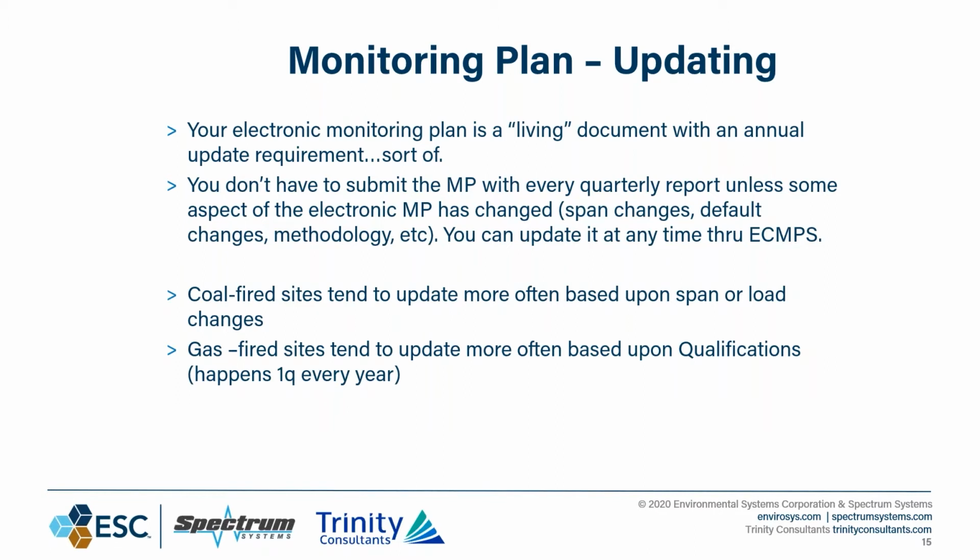Now, again, with talking about updating your monitoring plan, the electronic portion is a dynamic publication with an annual update requirement. You don't have to submit your monitoring plan with every quarterly report like you used to in the flat file days, unless some aspect of the electronic portion has changed: changes to spans on your analyzers, default constant changes, monitoring methodologies. You can update it anytime through the portal, through the reporting platform.